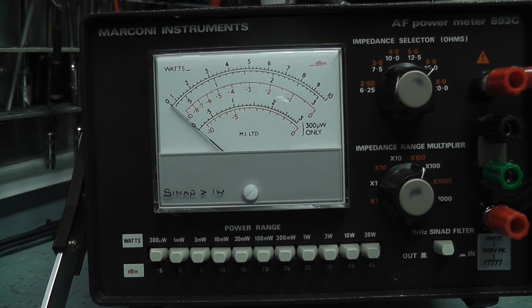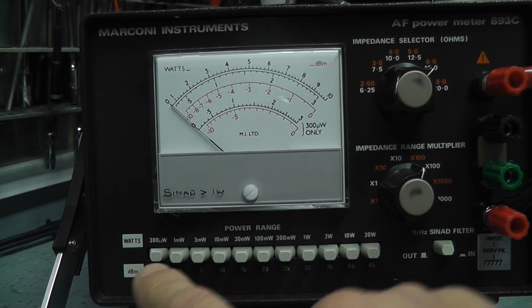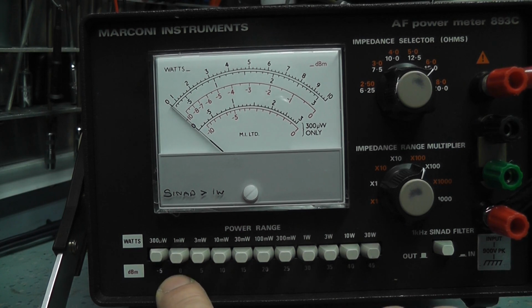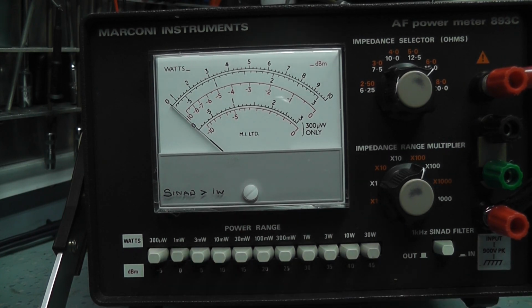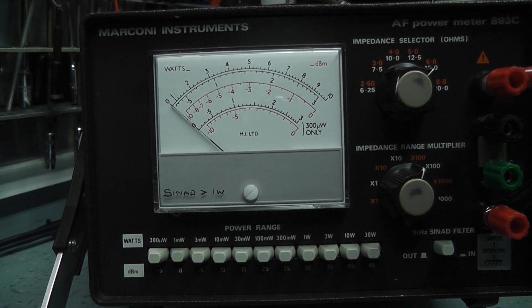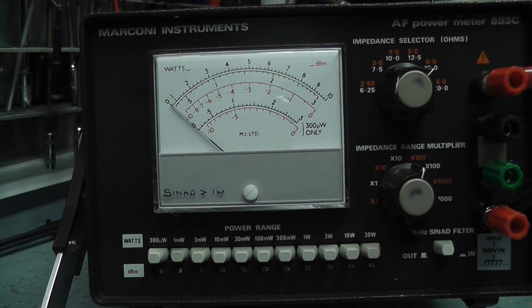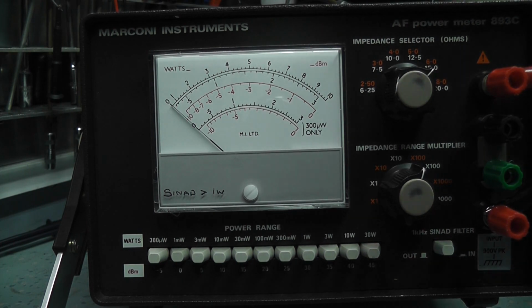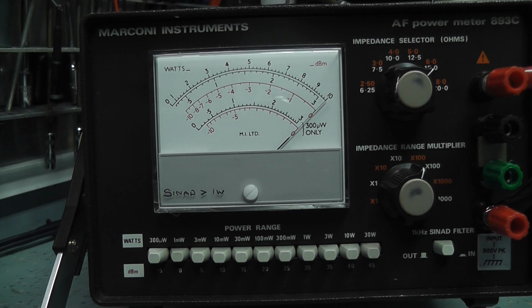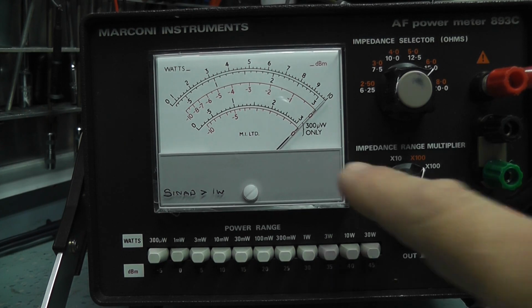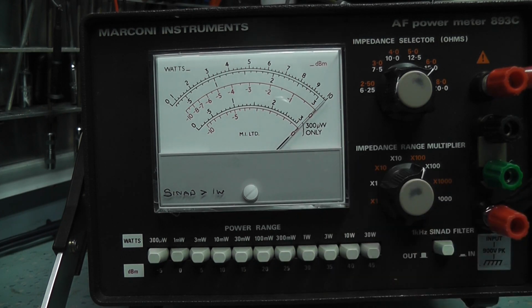So we're going to feed in a dBm signal of, I think we'll start at 0 dB. So if I press this button here on the bottom, that's our 0 dB button, and I'll type in our amplitude of 0 dBm, and then turn the output on. There you go. It's absolutely spot on at 0 dBm. So that's working correctly. Certainly seems to be working on that range okay.